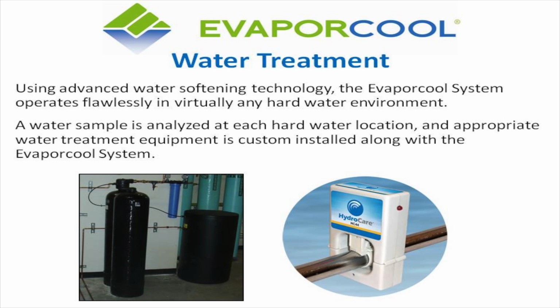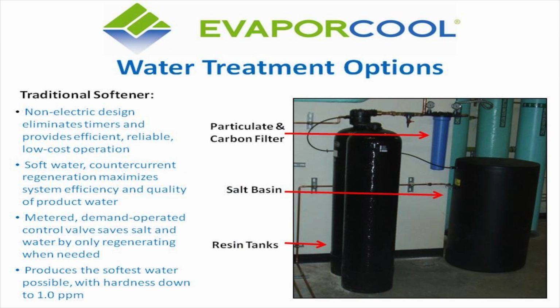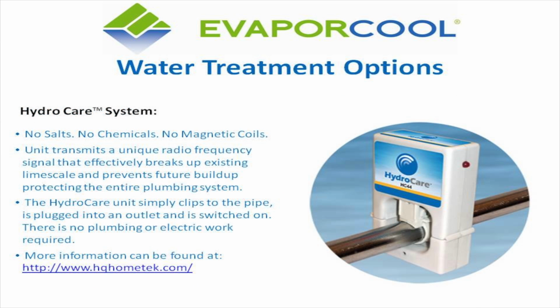We do require water treatment. That's the other thing. We can't just take standard water that's coming in from a pipe. We do have to have some type of water treatment system that will bring out the mineral content. So we have 2 systems we use. We either use a salt-based resin system or we use an ultrasonic system that's radio frequency that knocks out the minerals.